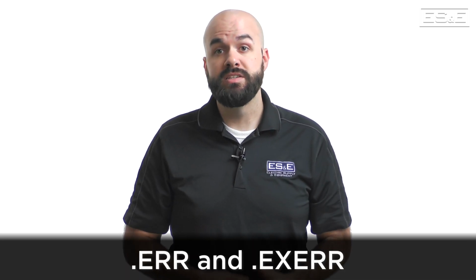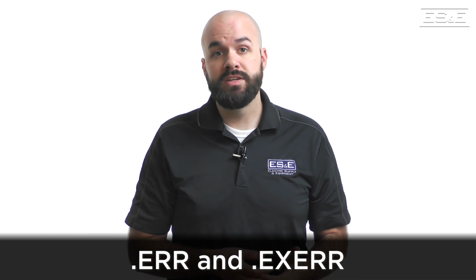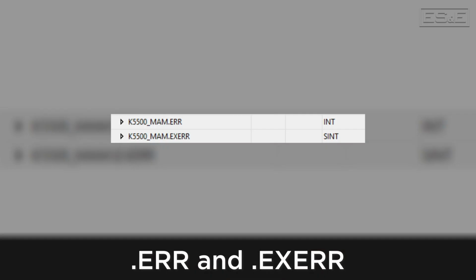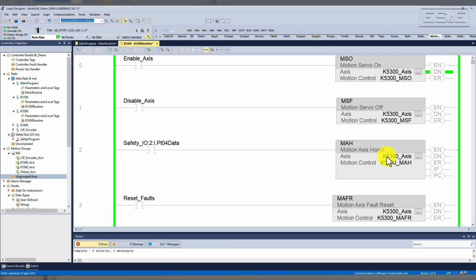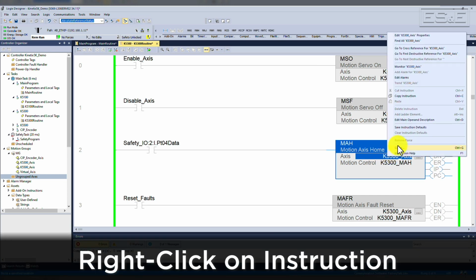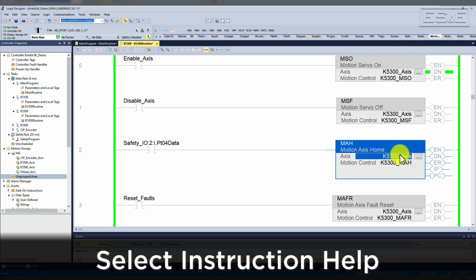A note about the error bit. Each instruction has two additional tags associated with the error bit: the .err and the .exerr. These are integer tags that will store specific error codes when the error occurs. There is a full list of instruction error codes that can be accessed via Logix Designer. By right-clicking on an instruction and selecting Instruction Help, you can find these lists.